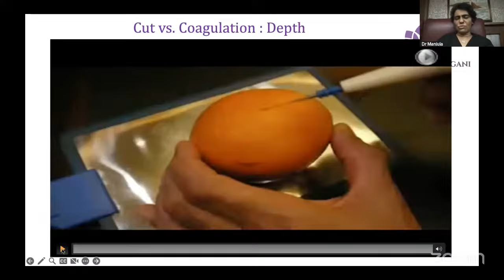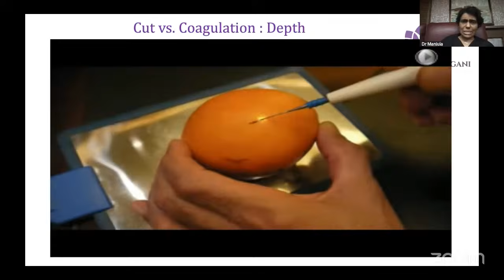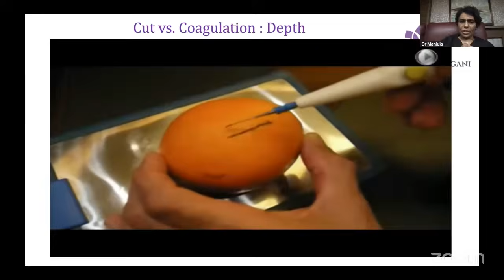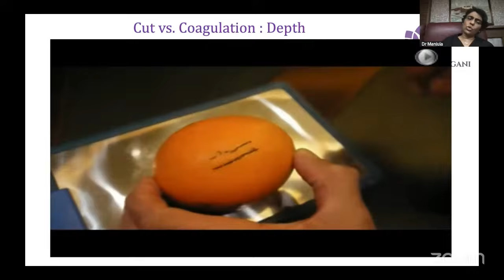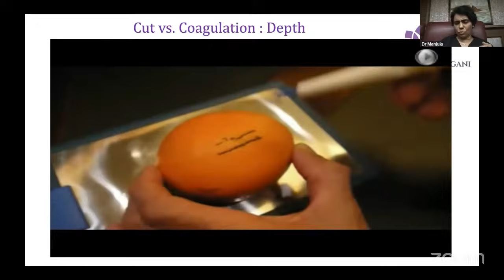Third, in the same vein, I want to show you some experiments which we did way back in 2006-07. This is the cutting current which we are using. The depth you see, you are using continuously. Now, to get the same effect with coag current, you don't get it. You have to use it 2-3 times to get the same effect. So the energy we use with cutting causes the best effect with the least damage. The number of times you have to apply coagulation is more.